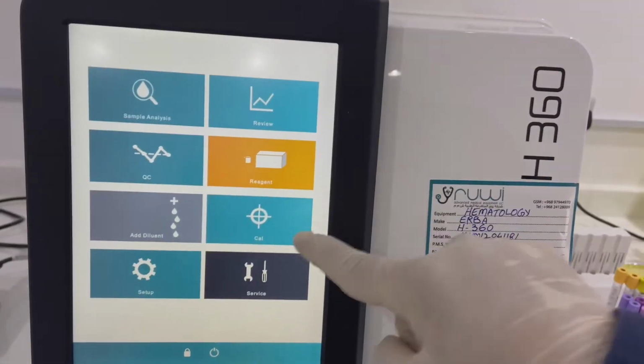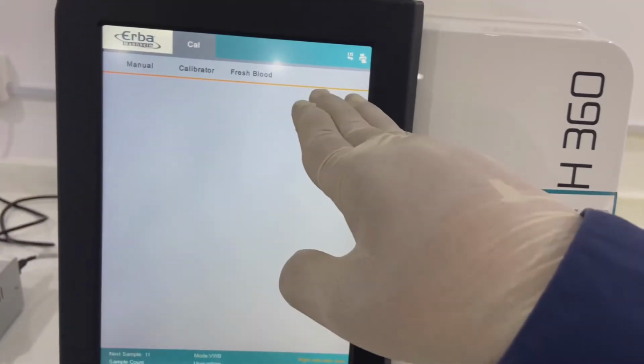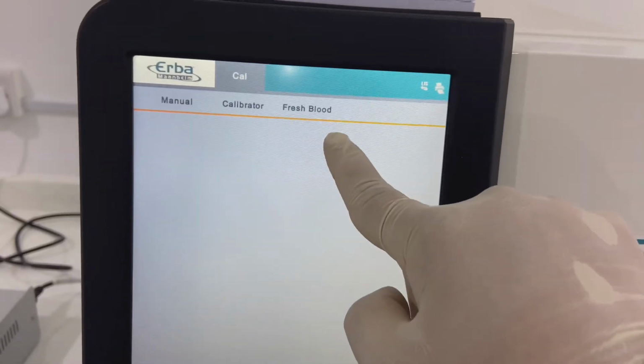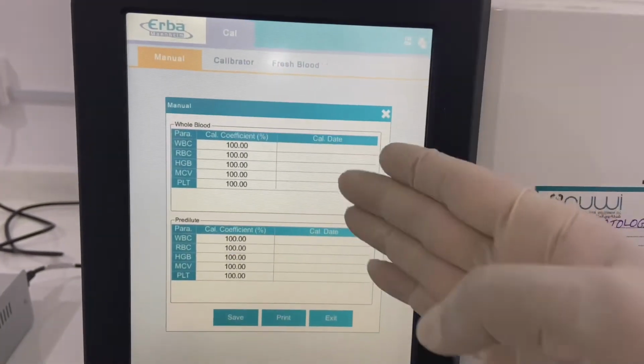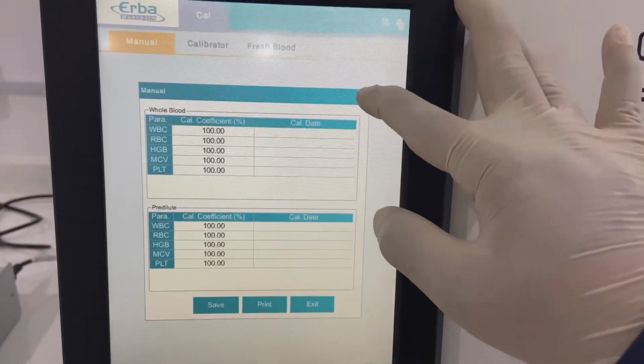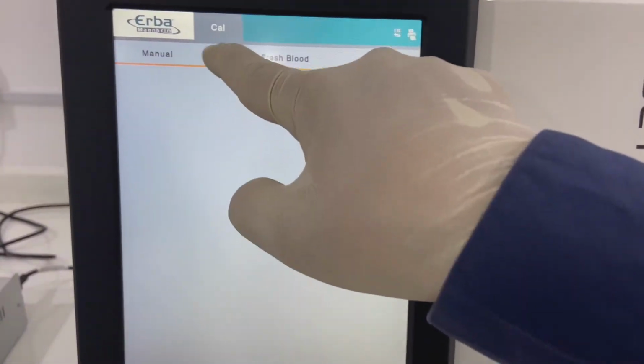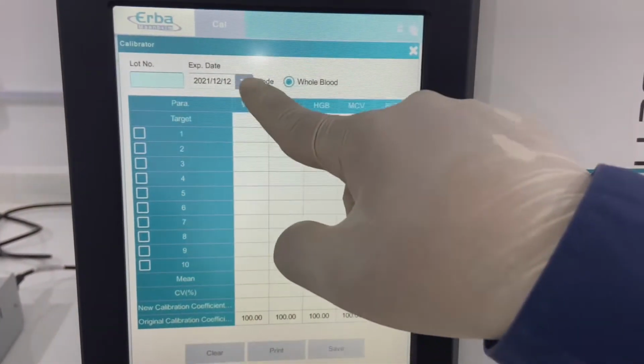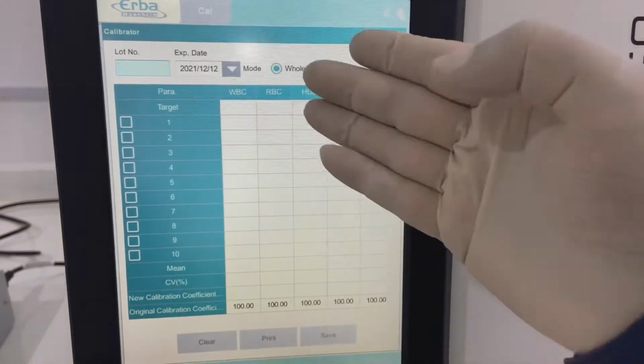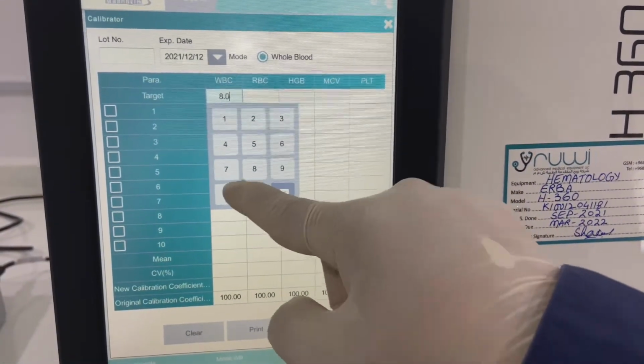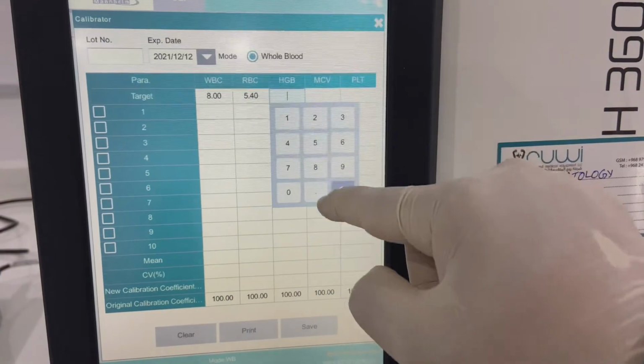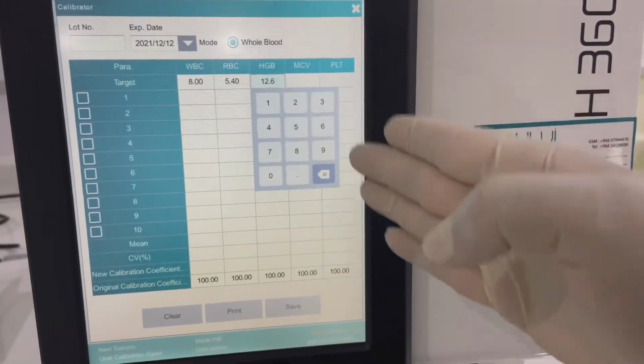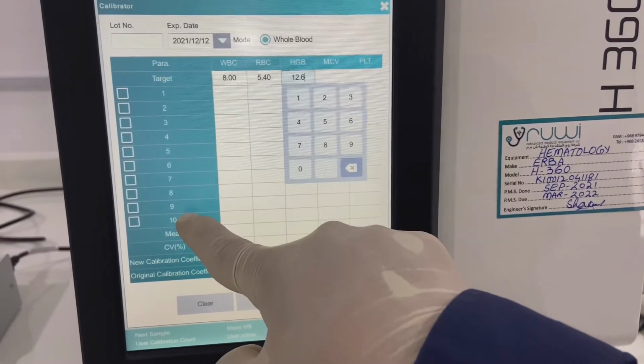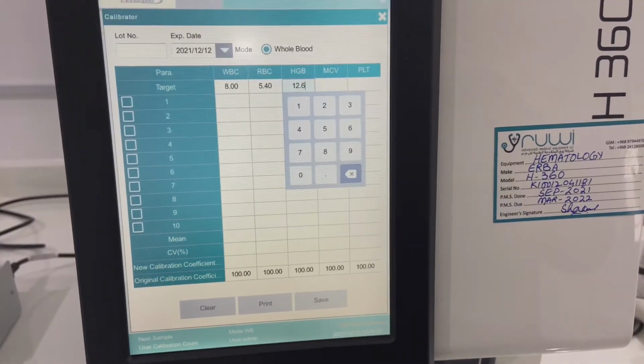Now we will see how to do the calibration of this analyzer. Click on Cal. There we have three options: manual, calibrator and fresh blood. If you click on manual, here you can enter the calibration factor by yourself manually as per the result. And if you want to do the calibration, click on calibrator, enter the lot number, enter the expiry and enter all these values like WBC, for example 8.0, RBC 5.4, hemoglobin 12.6 as per the paper, and then you need to repeat it 10 times. This is the way to do the calibration.